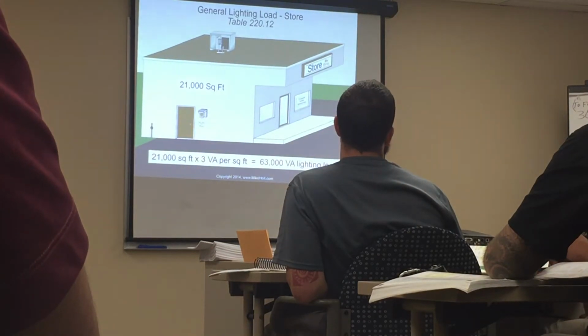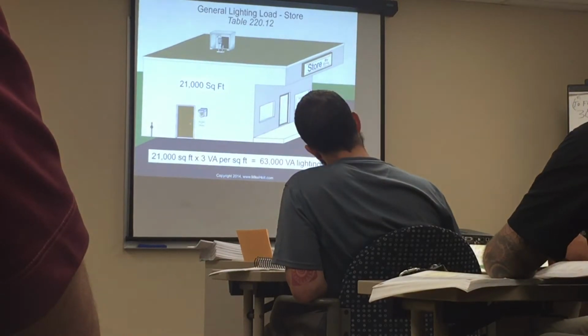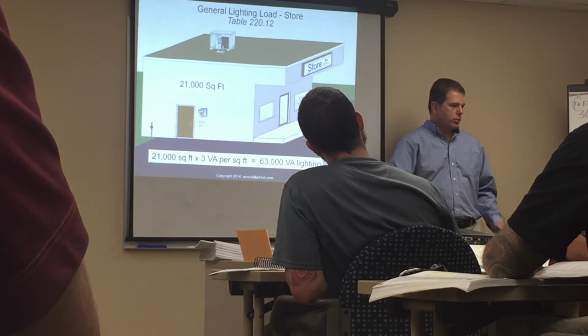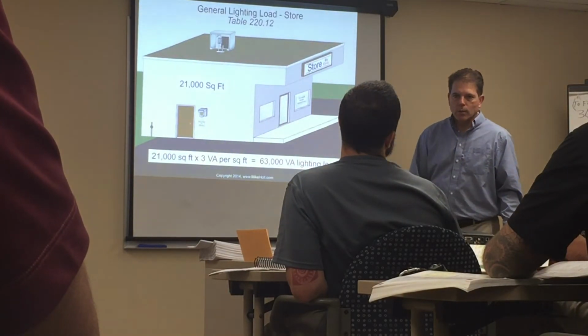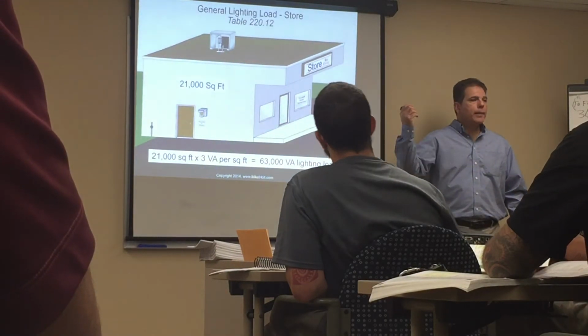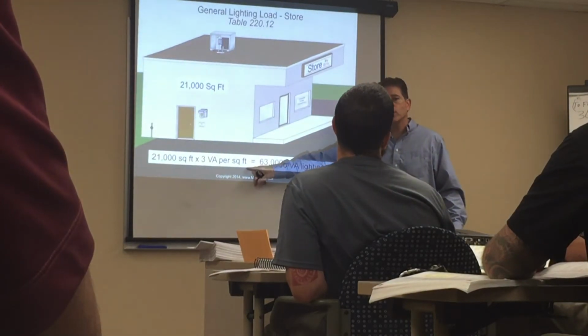Correct, yep, and here's the way the test will challenge you. They'll give you a store, and they'll tell you it has 100 fixtures, and each one of those fixtures is 1 amp. Okay, we now know there's 100 amps of load for the lighting fixtures. Now we gotta check to make sure which one's larger.